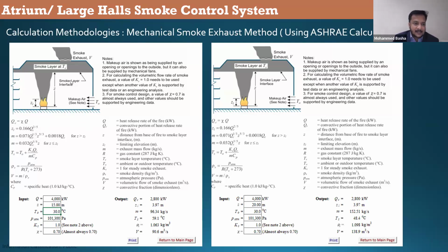So in the atrium, I want to maintain 15 meters. Why do I want to maintain 15 meters? I need to see the top floor, which is the top communicating space, 1.8 meters above the space. Why is 1.8 meters specified? Because it is the average human height. So the smoke layer shall be above the human height. So this 15 meters from here to the top, I'm considering including 1.8 meters for the occupant.